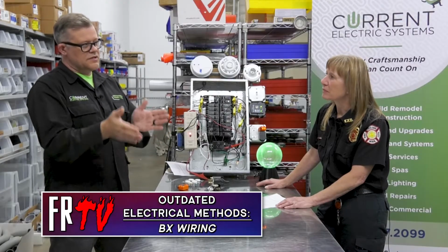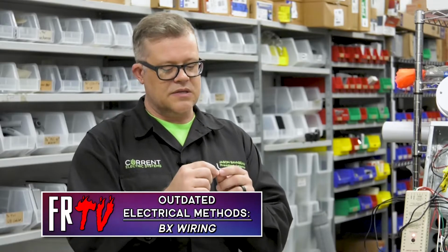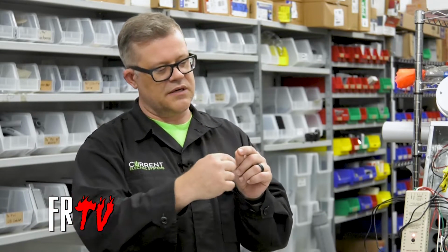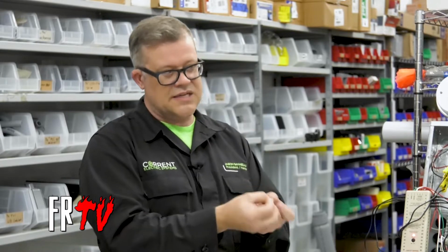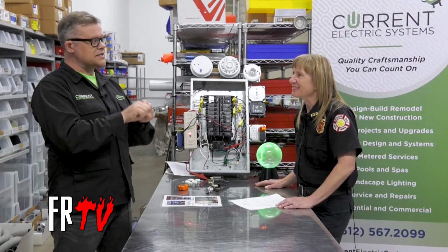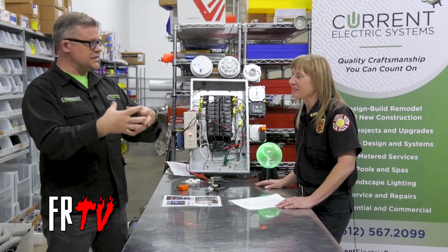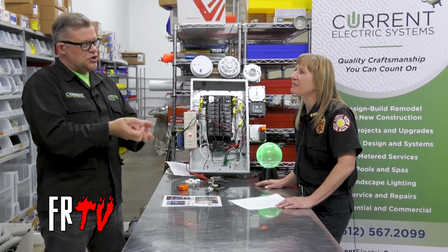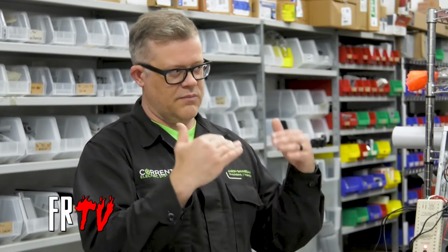The next step from there is called BX wiring. That is a steel jacket that kind of encircles the conductors, which are cloth, and they look similar to knob and tube. Because they're in that steel jacket and protected, and they're spliced in enclosures, if it's in good shape, like it's not burnt apart or everything's in usable condition, that insulation and everything will still perform to its voltage rating. So knob and tube, let's get rid of it. BX, let's take a look and make sure.